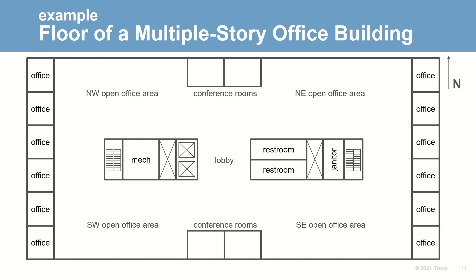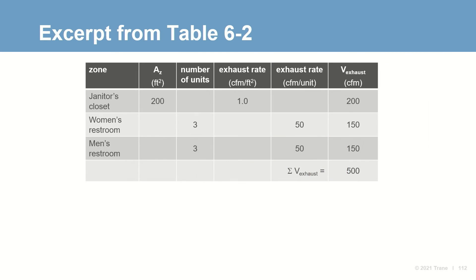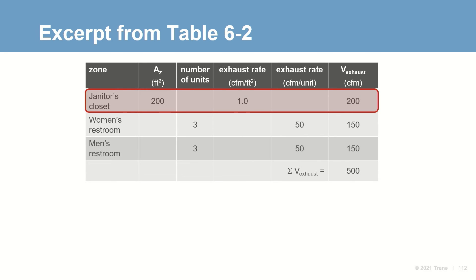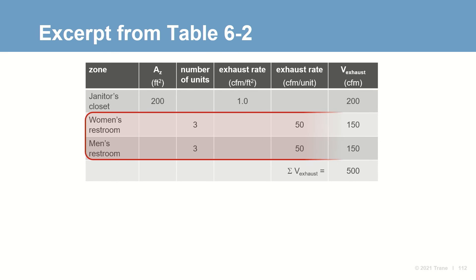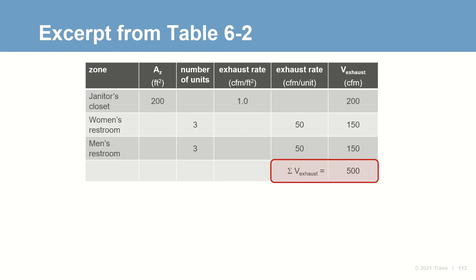Returning to our example office floor, recall that we have a janitor's closet and two restrooms. Based on the 1 CFM per square foot listed in the table, the exhaust air flow from the janitor's closet must be 200 CFM. Based on 50 CFM per unit, 150 CFM must be exhausted from each of the two restrooms. So the exhaust system must be designed for a total of 500 CFM.